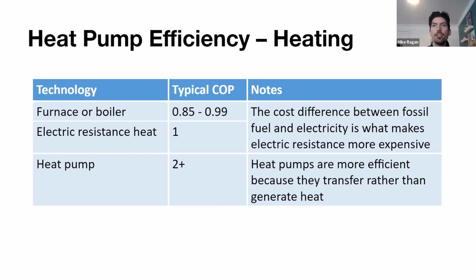And this, again, is because we're not generating this heat. We're powering our compressor to be able to cycle refrigerant throughout a system. If you have a system that has a heat recovery component, we'll be getting into that a little bit more in a bit, but that offers the ability to transfer heat from a zone that is in cooling to another zone that's calling for heating on the single refrigerant network. So if we have all this equipment in a server room and it's getting really, really hot in there, there's so much heat that we need to extract to cool the space. If that's on a heat recovery system with other zones, maybe just the general office area, that zone requires heating. Well, instead of ejecting all the heat we're removing from the server room to the atmosphere outside, we're going to transfer that to another zone that requires that heat. So that way we don't need to extract any more heat from the exterior space, and we're drastically improving the efficiencies of our heat pump system.